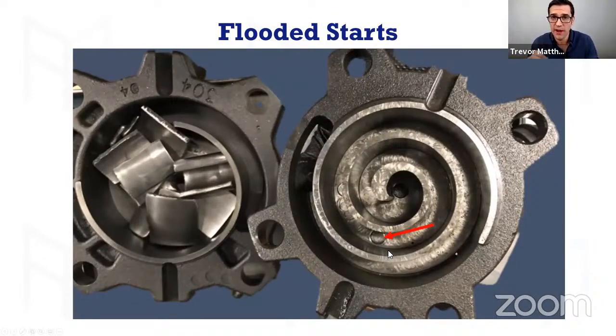If you open up a scroll, the way to open up a scroll is you cut 1/4 inch below, or 10 to 20 mils below, the weld mark seam on Copeland compressors. You cut around there. You've got to do it safely: safety glasses, shield, gloves. You can use a Sawzall or a zip cutter, a reciprocating saw. You cut around it and you take it off. But this would be this section here. If you look inside the compressor and you see scroll galling just like this, that means you had refrigerant go up there, wash the oil out, and cause metal on metal. You're not going to get oil in there ever again. If it looks like this, it's a flooded start. I mean a slug, sorry, because you're breaking the scroll sets.